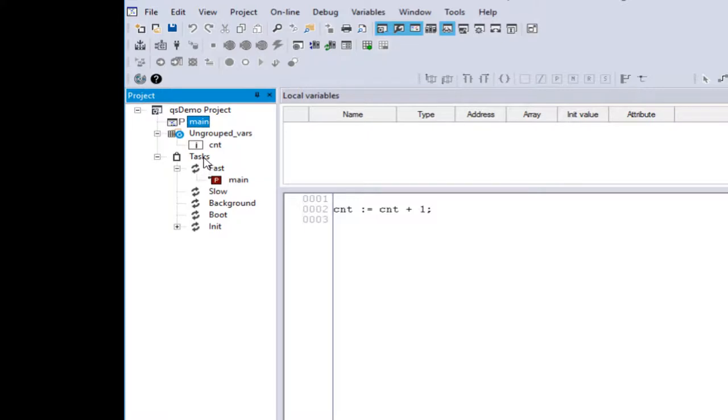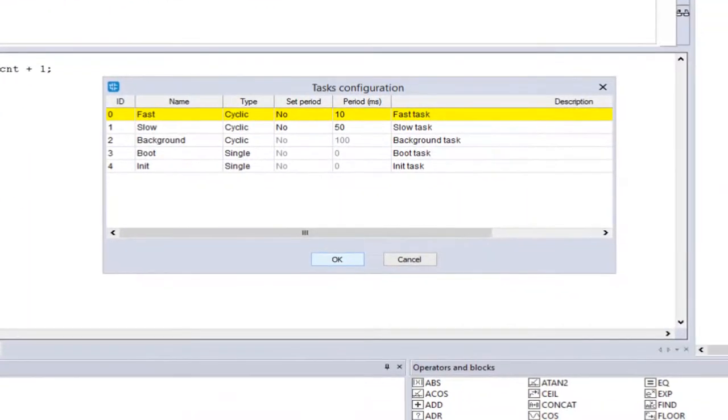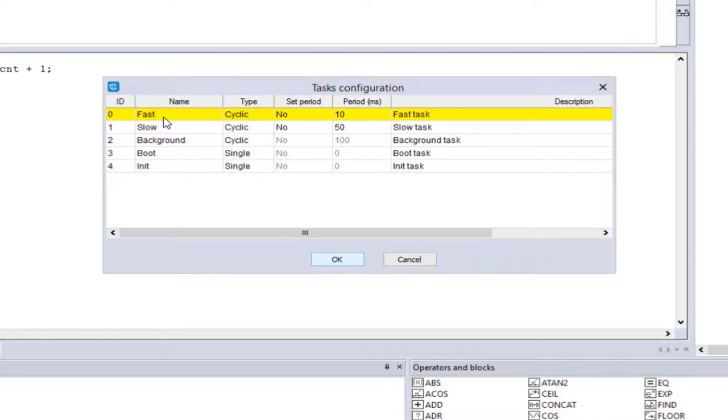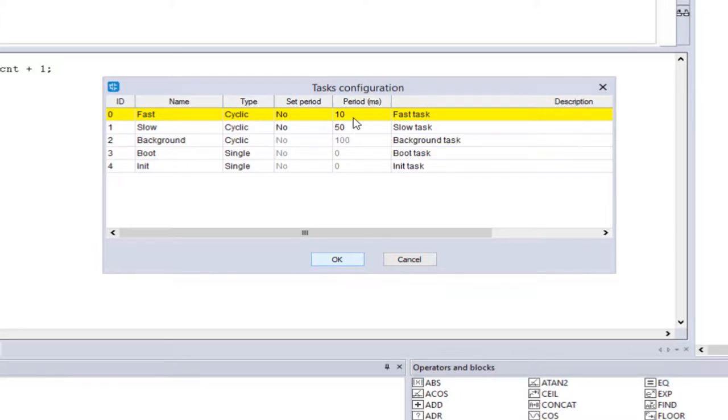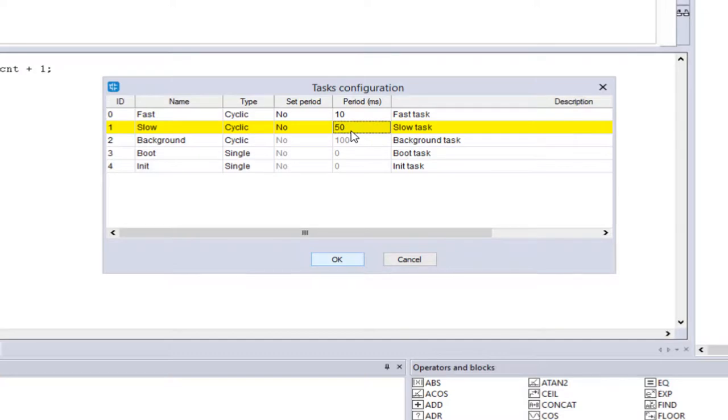One thing we can also do is click the task, double click it, and what we see is the actual time period that these tasks run at. So if we just concern ourselves today with the fast and the slow task, we can see that the fast task is running at 10 milliseconds, which is 10 times slower than our IO rate of one millisecond. And the slow task is running at 50 milliseconds, which is five times slower than our fast task. So this is where you're going to do things that aren't necessarily as critical as they would be in the fast task.